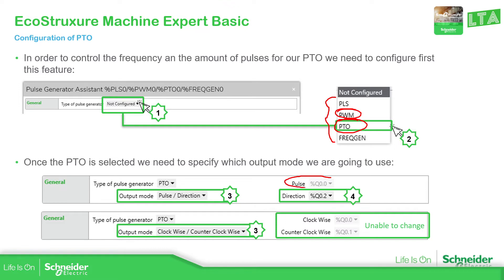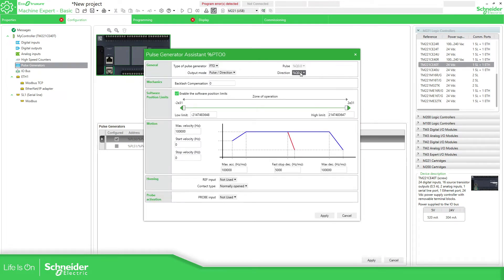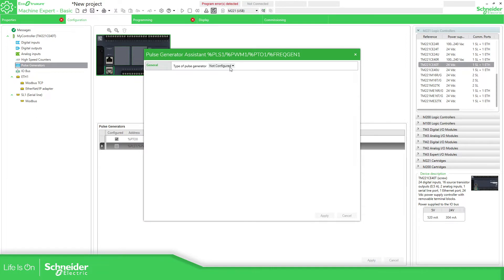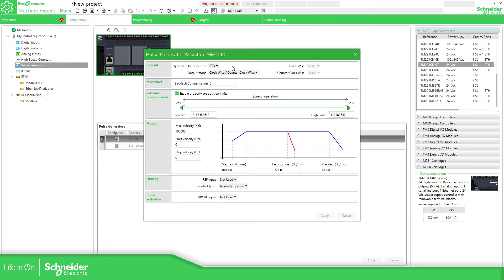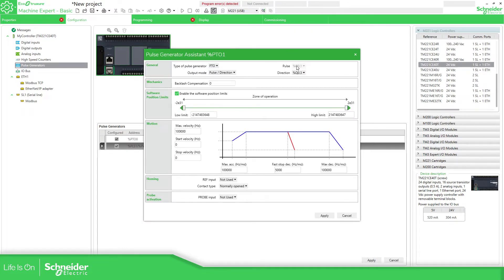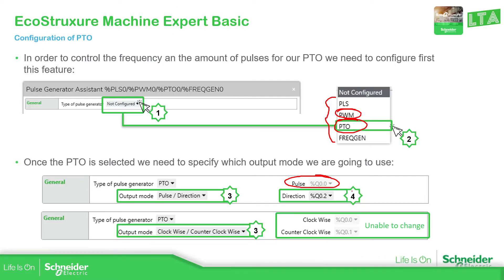Going back to the software: under pulse generation, selecting PTO with pulse direction allows you to use any of the outputs available for the controller. If you use counterclockwise mode, we only have one axis available and it won't allow another PTO. But if I use pulse direction, it allows me to configure another axis, taking the second fast output, giving me two axes.